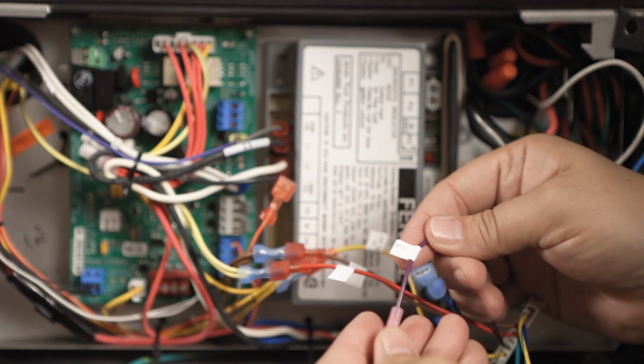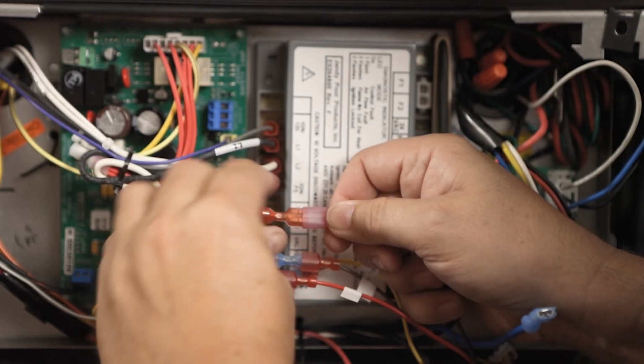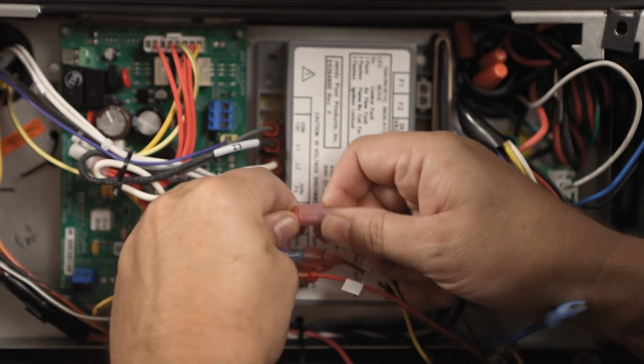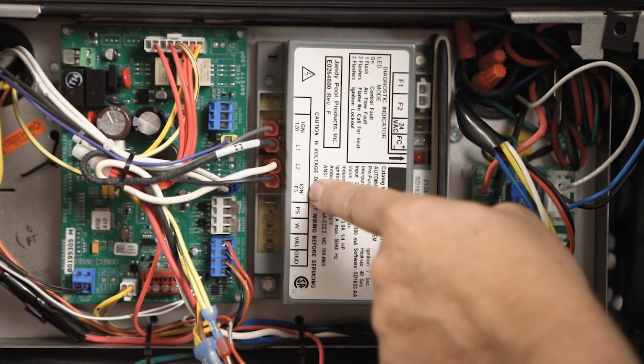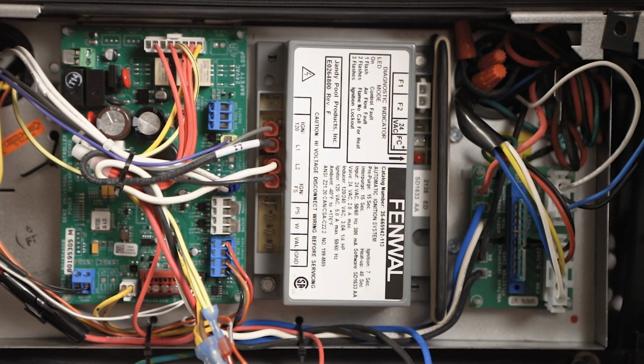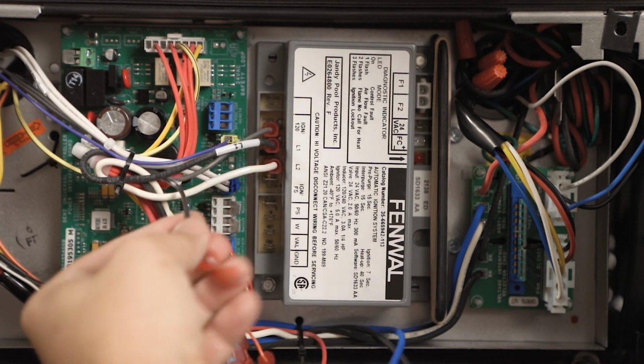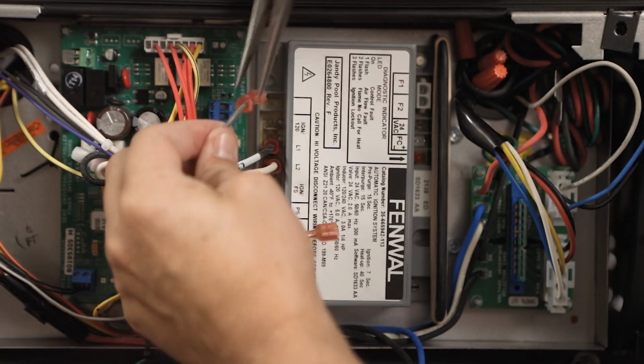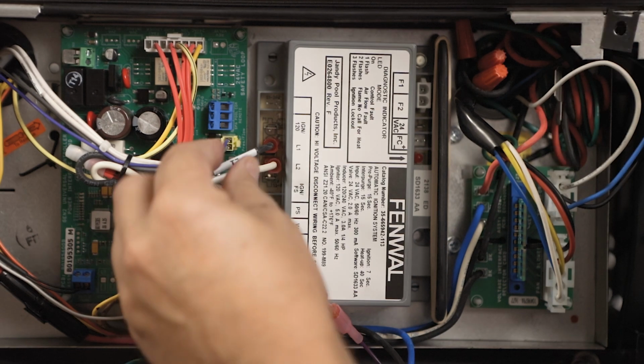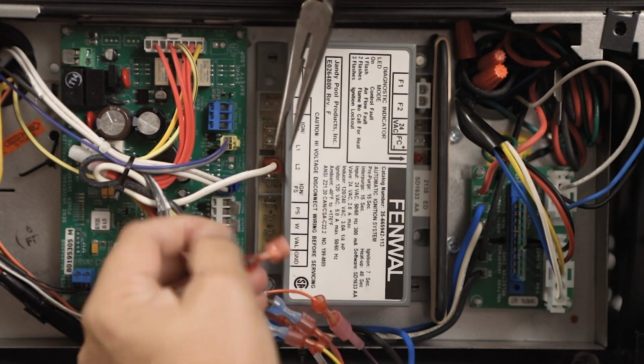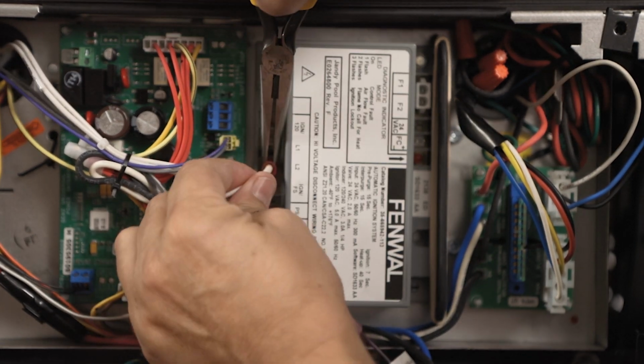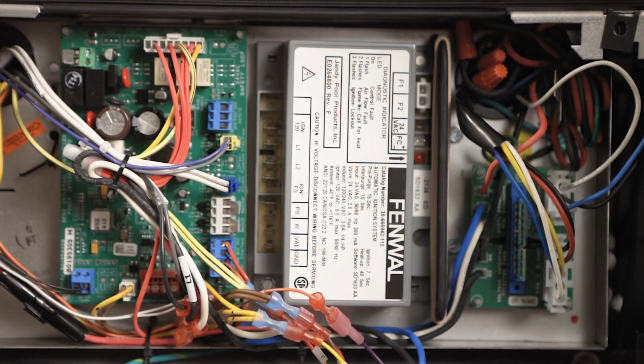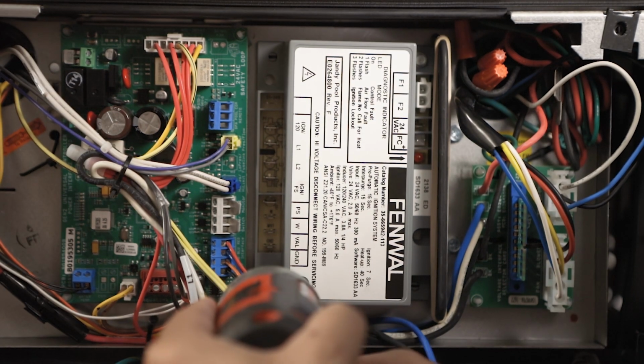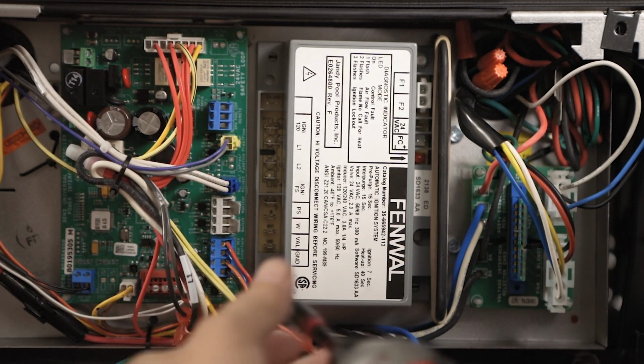Connect the PS wire to the 11-pin harness wire labeled PSI or pressure switch in. Next, remove the igniter wires from the terminals identified as IGN/FS and IGN/120. And finally, remove the 120-volt power wires from the terminals identified as L1 and L2. Once all wires have been disconnected, remove the existing module.